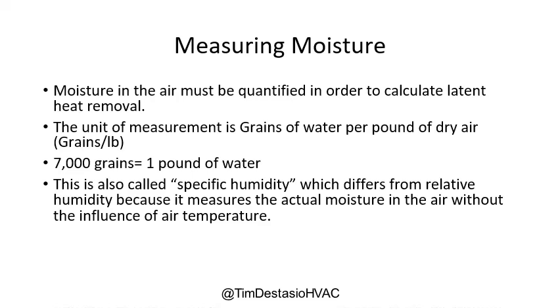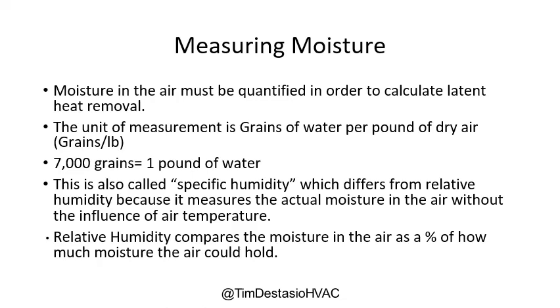Specific humidity differs from relative humidity. Specific humidity measures the actual moisture in the air — the actual number of grains of moisture — without the influence of air temperature. Relative humidity compares the moisture in the air as a percentage of how much moisture the air could hold. Think of it like a sponge: if you pour a cup of water on a very large sponge, the cup of water is your specific humidity, and when you pour it into the sponge, that ratio of how much water the sponge holds compared to how much it could hold is your relative humidity — a percentage.